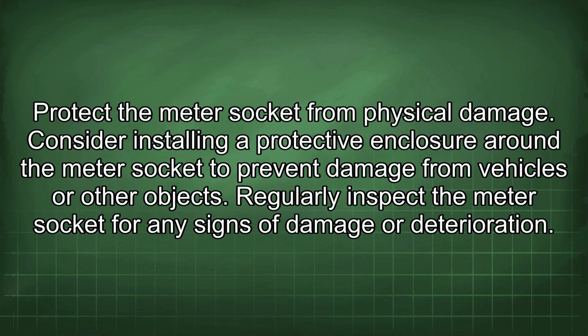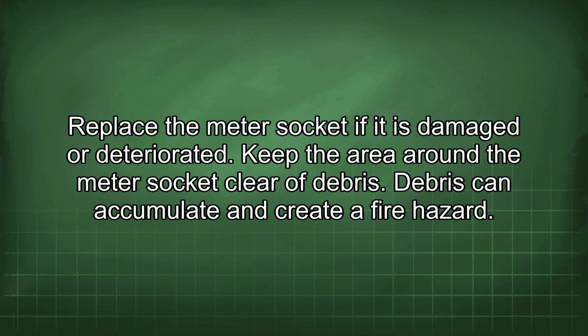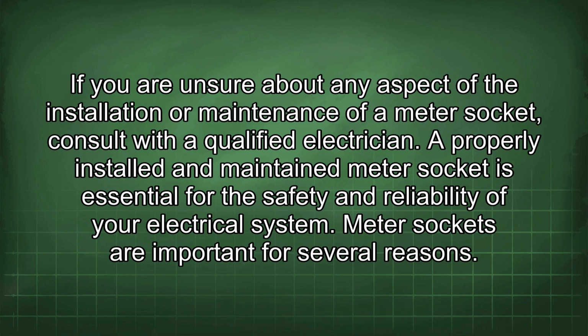Protect the meter socket from physical damage. Consider installing a protective enclosure around the meter socket to prevent damage from vehicles or other objects. Regularly inspect the meter socket for any signs of damage or deterioration. Replace the meter socket if it is damaged or deteriorated. Keep the area around the meter socket clear of debris. Debris can accumulate and create a fire hazard. If you are unsure about any aspect of the installation or maintenance of a meter socket, consult with a qualified electrician. A properly installed and maintained meter socket is essential for the safety and reliability of your electrical system.